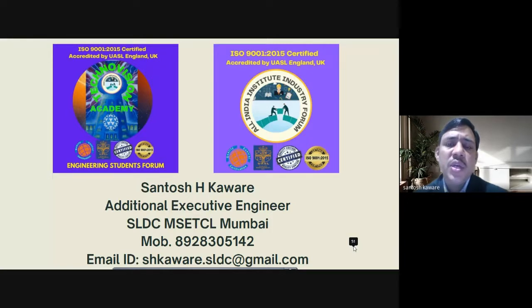He will come. If I want to energize a new line, new transformer, new equipment, then actually I have to apply. They will come to our station. They will inspect all the things. They will check the results of the test, and then they will give the permission to charge the equipment. So we don't have such facility, but some possible tests that can be carried out, we test here in the substation also.